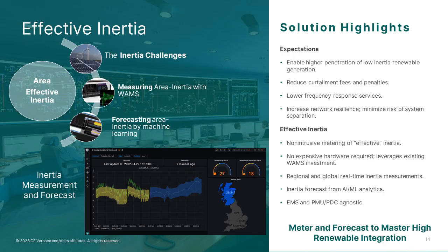The effective inertia application uses the high fidelity frequency data and the flows data, and through that variability, it's able to measure in real time the inertia on the grid. We use the word effective inertia because it's taking into consideration not just the synchronous generation that's online, but also accounts for any other source that brings inertia to the grid. This could be frequency dependent load. This could be your renewables providing some level of inertia on the system.